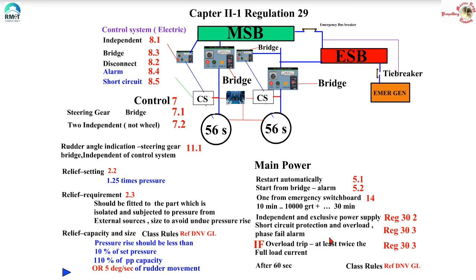If an overload trip is provided, it should not be the conventional one that trips at 110% overload. The steering gear motor overload should be minimum 200% — at least twice the full load current — with an extended time delay. SOLAS doesn't define the time delay, but class guidelines say after 60 seconds the overload trip can kick in. That is a big difference from, say, a sea water pump rated at 110% with a much shorter time lag. So let us not jump to the conclusion that a steering gear motor should never have an overload trip — that is not true.